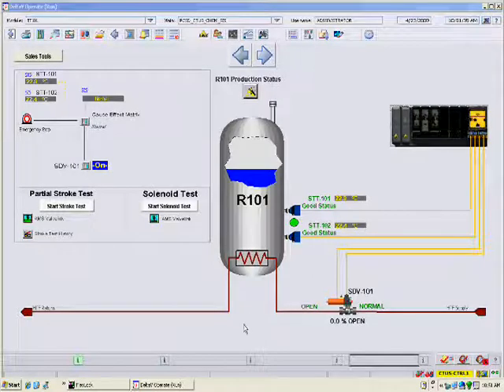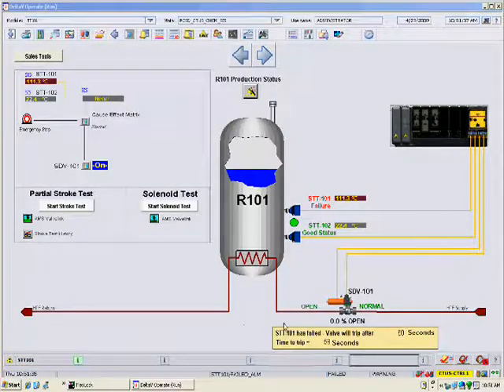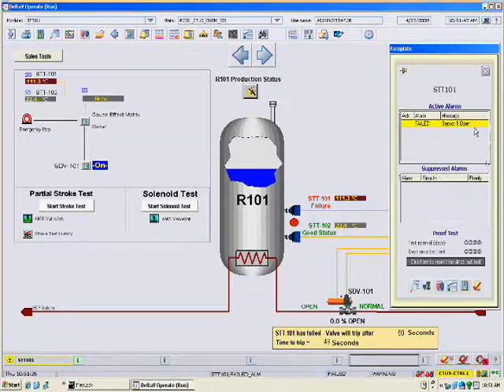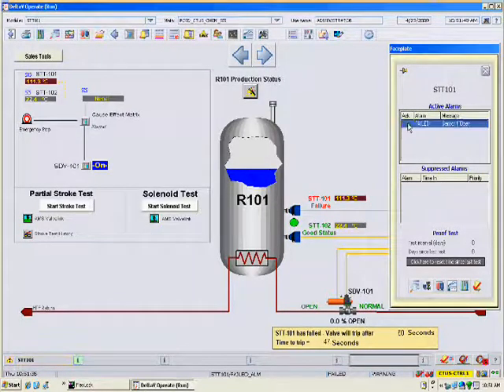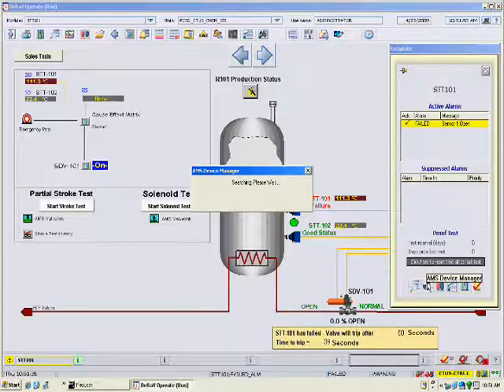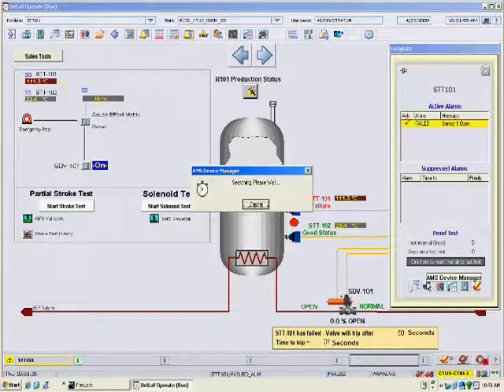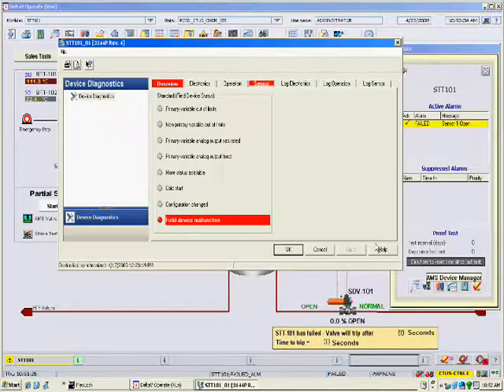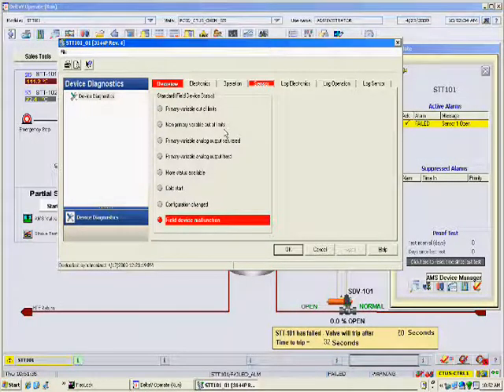Now let's look at a HART protocol temperature transmitter in a safety instrumented system. The system is continuously monitoring the health of all HART devices. The device alert appears and the operator clicks on the alarm banner, which opens the device faceplate. In this case, the faceplate shows it is a serious device failure, not a process problem. Without device diagnostics, the failure would masquerade as a process problem and likely trip the shutdown valve. The operator opens detailed diagnostics at a click of a button. The diagnostics page is designed by the device manufacturer using EDDL.